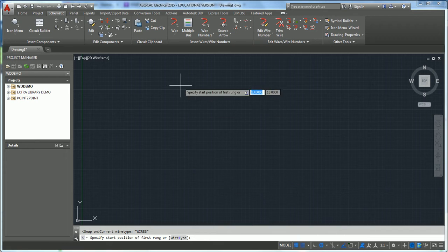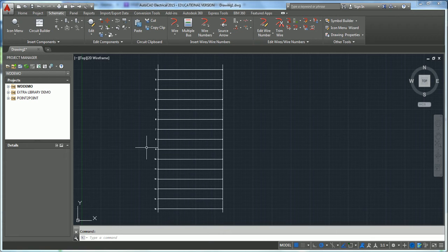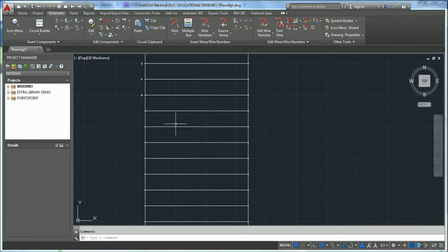Go ahead and click OK. You can control the width — we're going to make this ladder 8.5 wide. Your spacing between rungs, which are your horizontal lines, we're going to make 1.25 to put a nice spacing between them. I like to start my first reference at 1, index at 1. We're going to hit OK, left click somewhere, and scroll down to make as many rungs as you want. If you feel like there are too many rungs, you can go to Add Rung or Revise Ladder — say I only want five rungs — hit OK and it changes to five rungs.